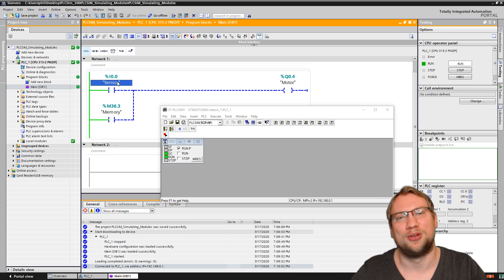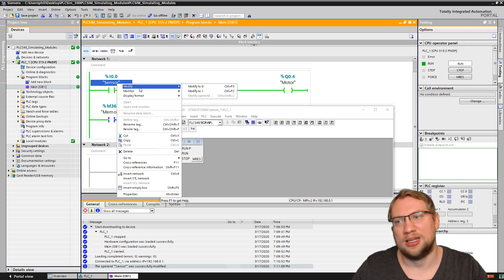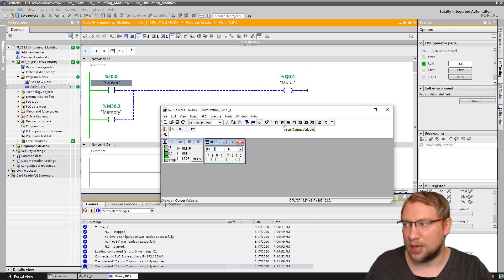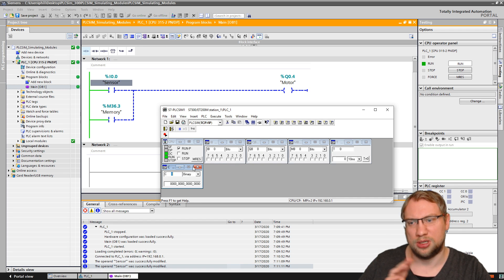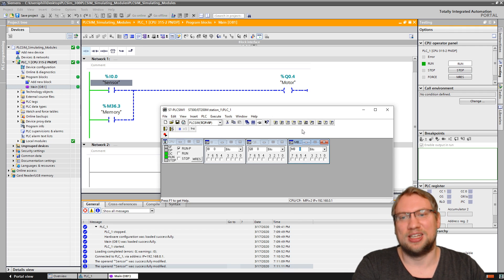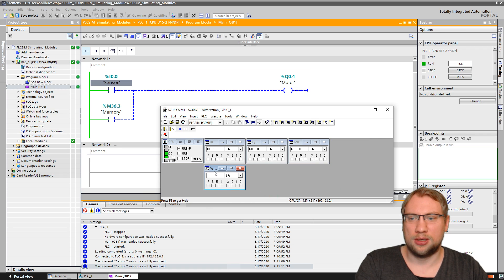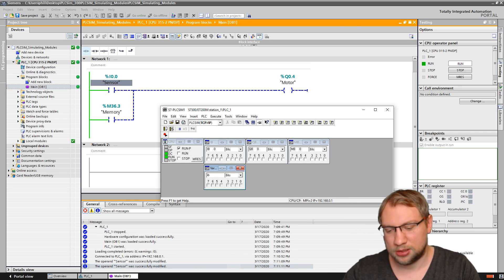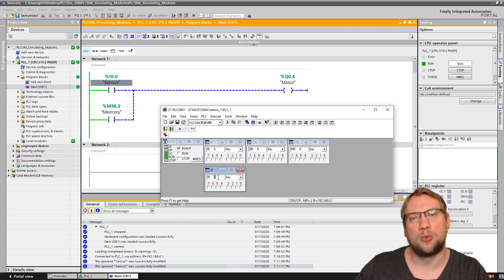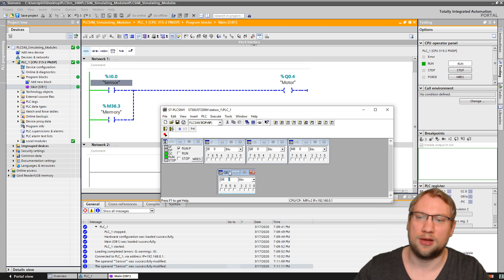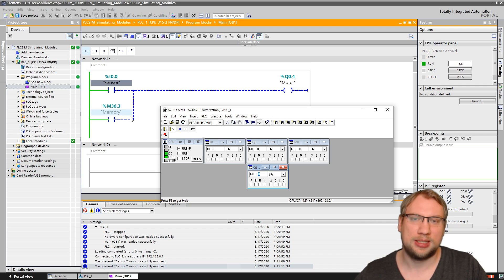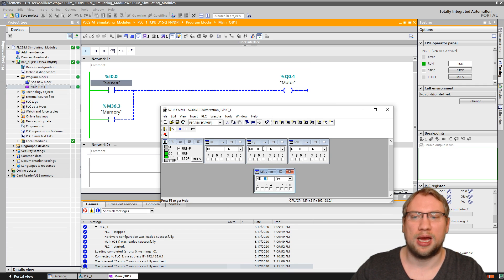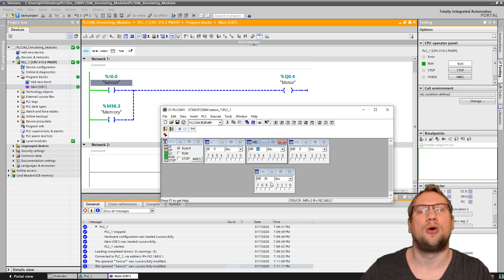In the simulation, I want to turn on sensors. I could right-click and modify to one, but that's a bit annoying. This tool lets us add an input byte, output byte, memory byte, timer and counter — though I don't recommend those timers and counters; use the standardized ones. There's also a generic variable. They all look basically the same. In a generic one, if I type IB — which is input byte — zero and hit Enter, it's the same as the input byte window. If I type QB zero, I get the output byte. For memory I'm using M36, so I type MB — memory byte — 36 and hit Enter. All of these windows are basically generic variables.